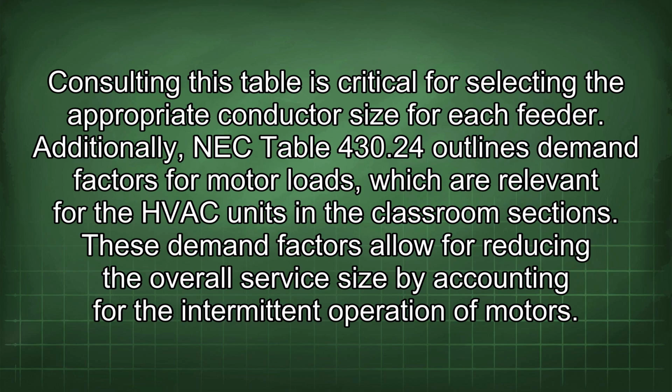Additionally, NEC Table 430.24 outlines demand factors for motor loads, which are relevant for the HVAC units in the classroom sections. These demand factors allow for reducing the overall service size by accounting for the intermittent operation of motors.